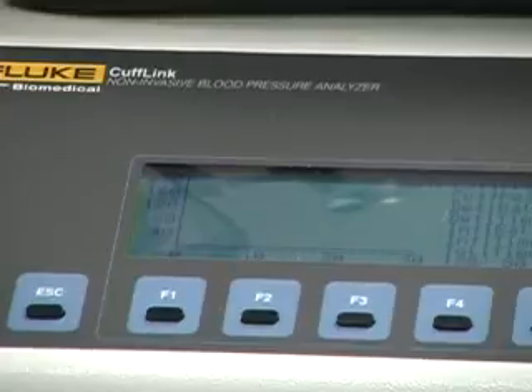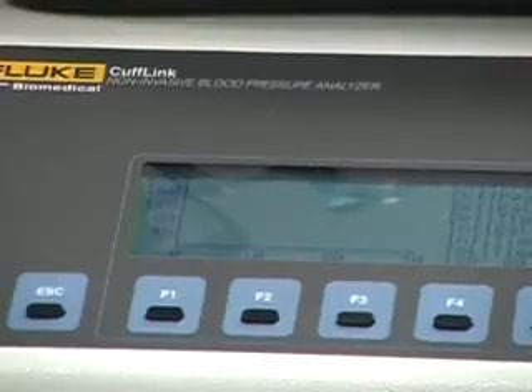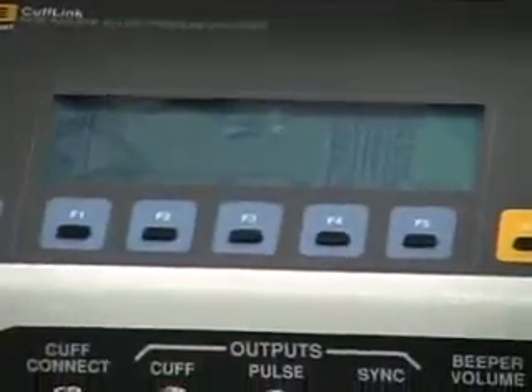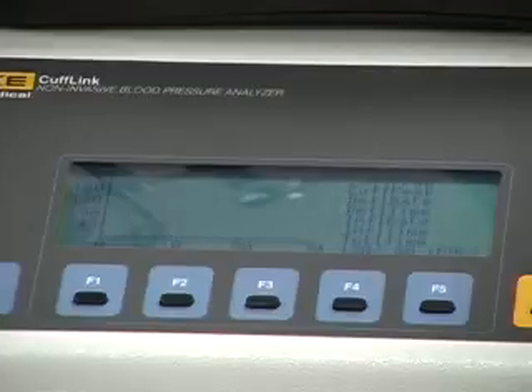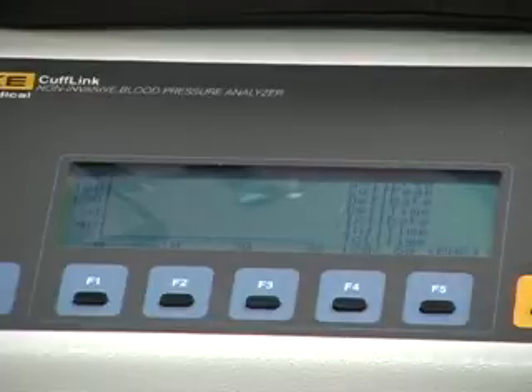And with it, it's going to take longer for the monitor to measure that blood pressure, because the technology used in the monitor is based on a stepped deflation of the cuff pressure. After it initially pumps up to the peak and begins to deflate, it'll sit at one static pressure level until it has 2 beats that are very close to the same amplitude. Once that happens, it says, okay, I've got a good pulse. Clear beats. Let's go down some more pressure. Get 2 more good beats. Go down 2 or 3 more millimeters of mercury. Get it again, and just keep going that way.